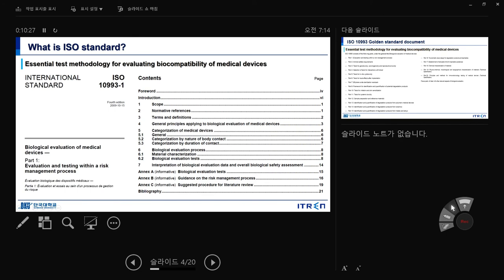The ISO standard document always shows: scope, reference terms, general information, and from part 5 onward it specifies in detail how to study and evaluate your material — specifically mentioning protocols, sample size, time, culture period, media, and other parameters. ISO 10993 has more than 3,000 pages of very specific dimensions. This is the first page of the ISO standard, and they have many editions.